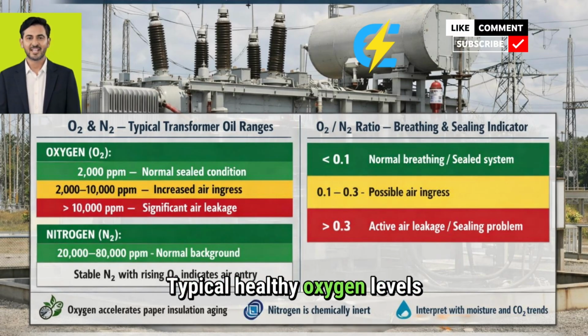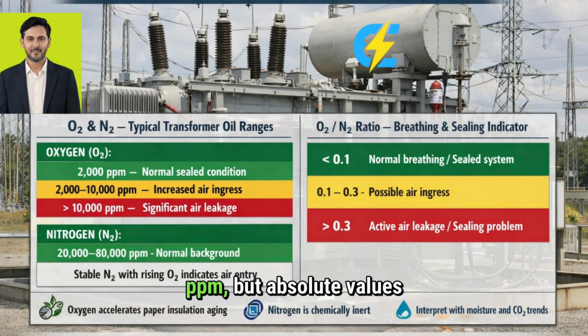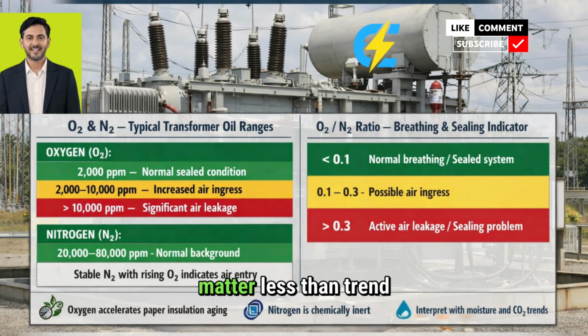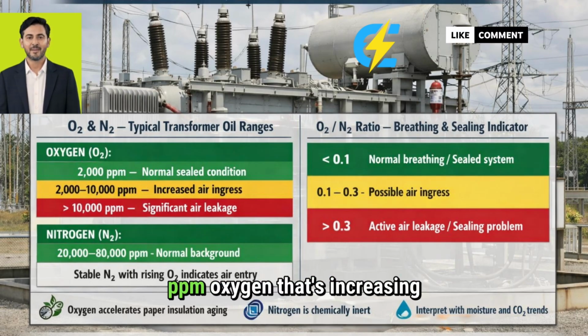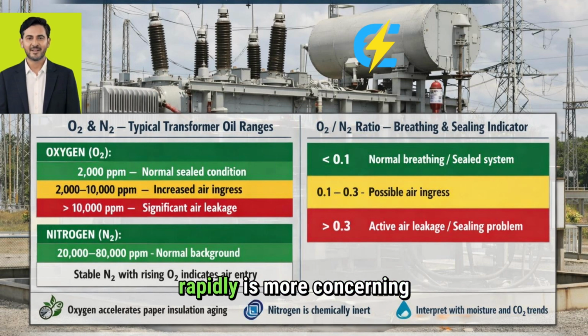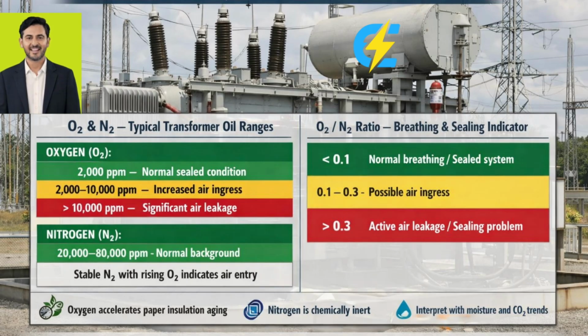Typical healthy oxygen levels are usually below 1000 ppm, but absolute values matter less than trend and ratio. A transformer with 500 ppm oxygen that's increasing rapidly is more concerning than one with 800 ppm that's remained stable for years. Nitrogen should remain stable once the system is sealed. Any significant increase in nitrogen indicates fresh air ingress.